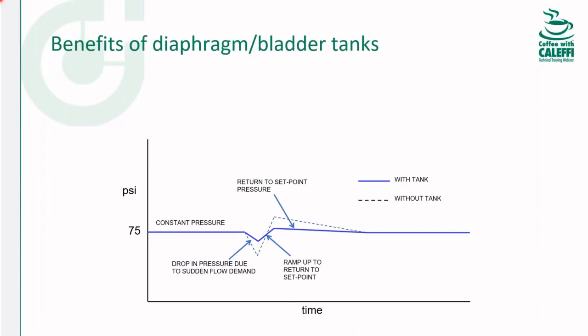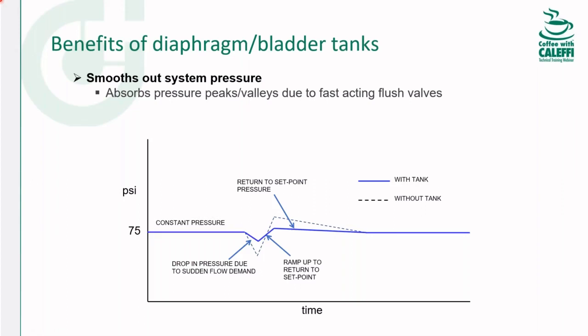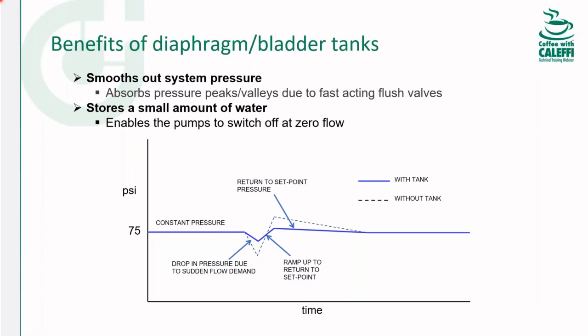All right. So I figured we'd jump into diaphragm and bladder tanks. For those of you paying attention, you probably saw those in the pictures above. And I know this question came up on the registration survey, so let's dive in here. So what do diaphragm tanks do? First off, they help smooth out the system pressure when you have flush valves and other fast-acting devices on the system, especially when you have fast-acting valves located far away from the pressure transmitter. Think cooling tower makeup valves on the roof. So the tanks also store a small amount of water, and that gives the pumps time to ramp up and take over the load demand when you see quick demands.